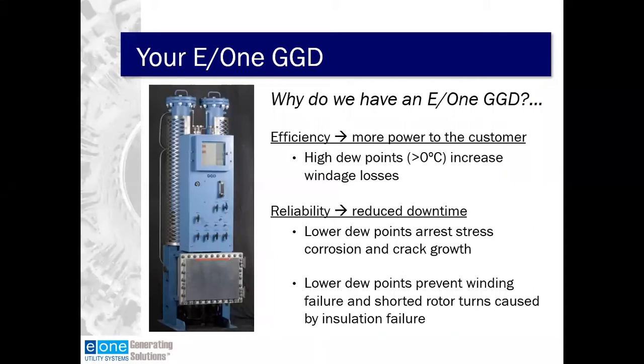You also have higher reliability. We want to reduce downtime at all costs. So a generator gas dryer is there to minimize these risks. And one of the main risks we have is stress corrosion and crack growth, particularly on the retaining ring. Another failure mode is associated with end winding failure and shorted rotor turns that are a result of insulation that has failed due to higher dew points in the generator. So two very key reasons, efficiency and reliability of your generator, for having a generator gas dryer in your plant.